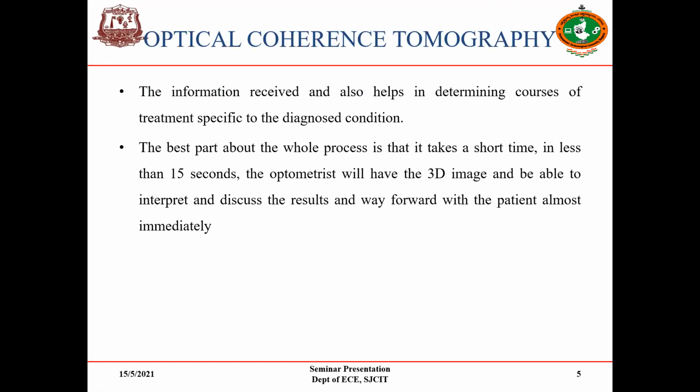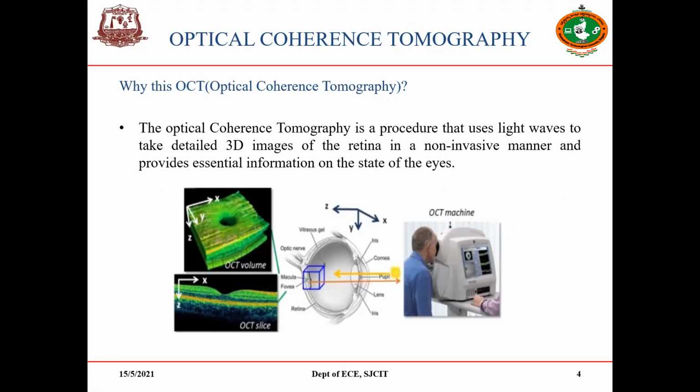Then, how does optical coherence tomography work? It is the spectral domain, and this domain provides 2D and 3D images, and it uses a long wavelength and broad bandwidth light to illuminate the retina and access the light reflected from the retinal tissue.